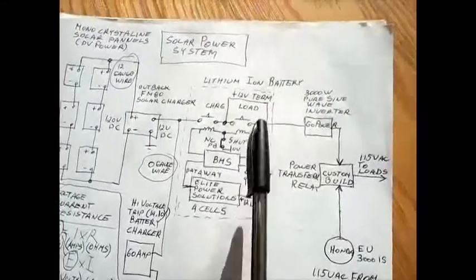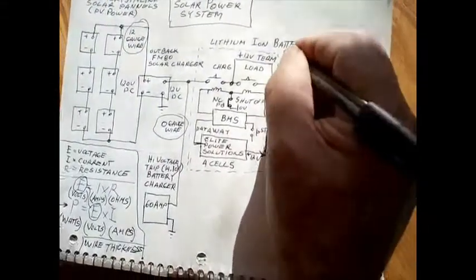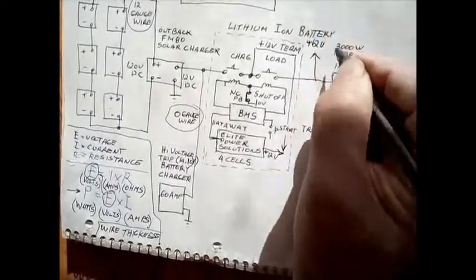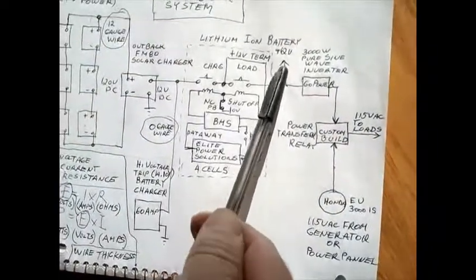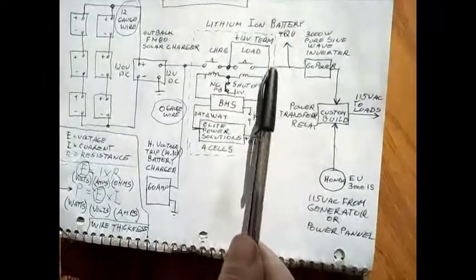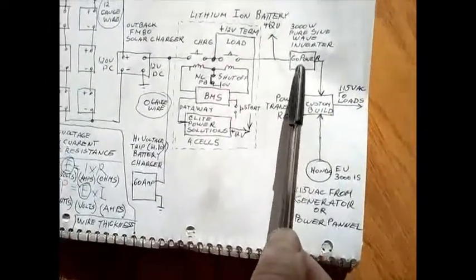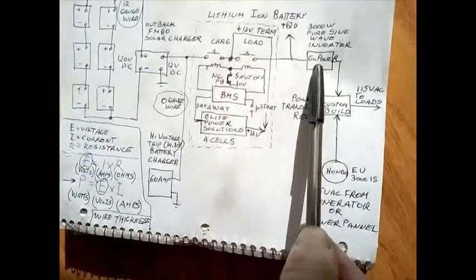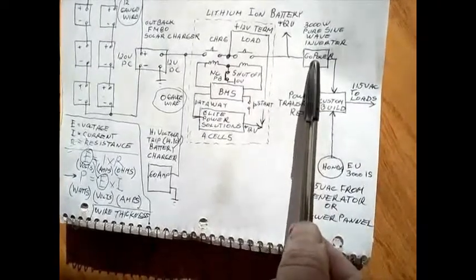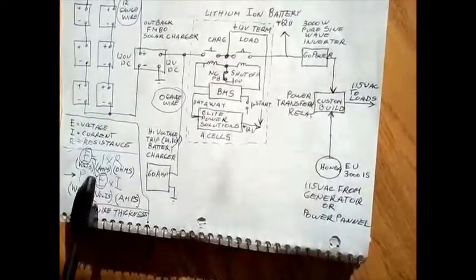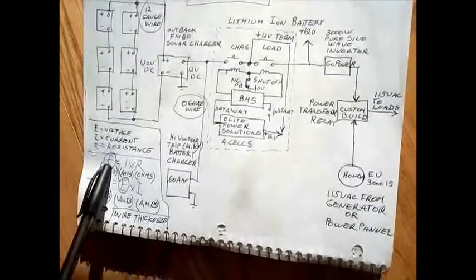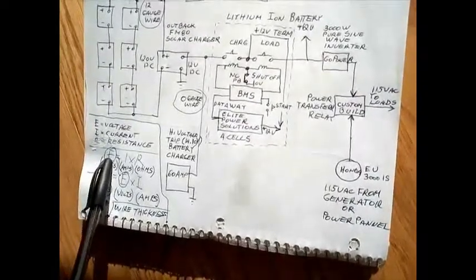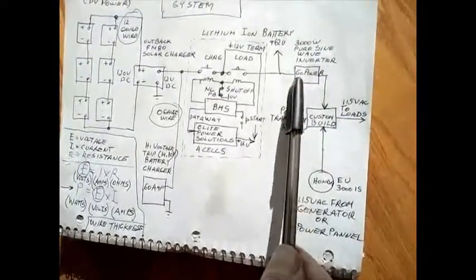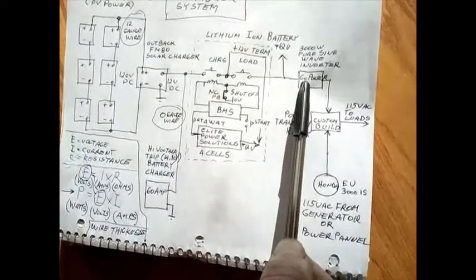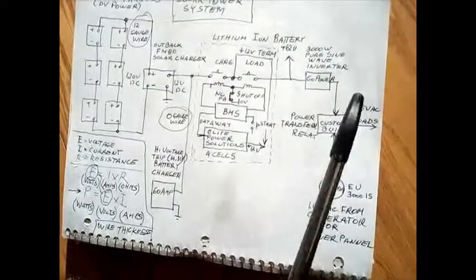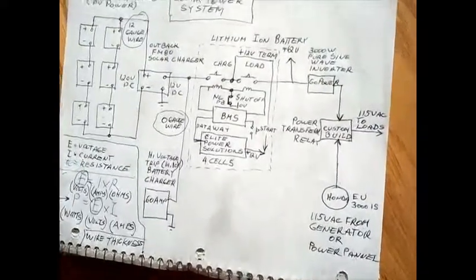Now, in the load circuit, there's also 12 volts DC. The pump, the macerator pump, the water pump, some of the lighting run off the 12 volt circuit. And then we have the power inverter. Again, we're using super heavy gauge wire, because we've only got 12 volts to play with. With 12 volts, we're dealing with high currents. When you have high currents, the voltage drop becomes very high as well. For the inverter, the most important thing that I would recommend is that you make sure you have a pure sine wave inverter. Some electronics will not work on modified sine wave.